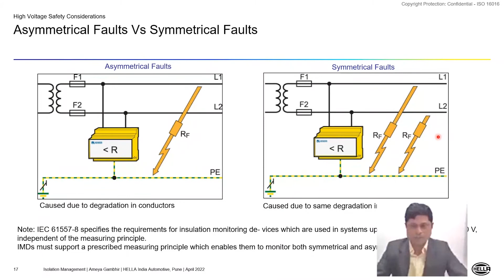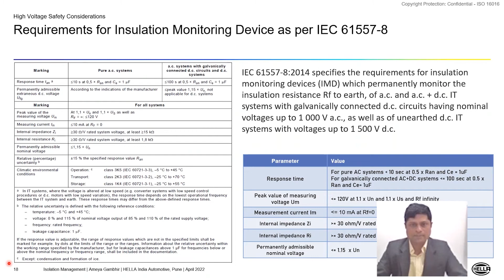Okay, so this is the IEC 61557-8 standard. I understand this may not be readable, so I have just taken a summary of this. Basically, this standard talks about response time for AC as well as AC plus DC system. This standard talks about peak value of the measuring voltage, measurement current range, impedance range, basically AC impedance and DC resistance range. So this is basically the master standard for the insulation monitoring devices.